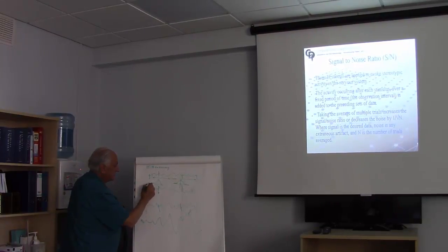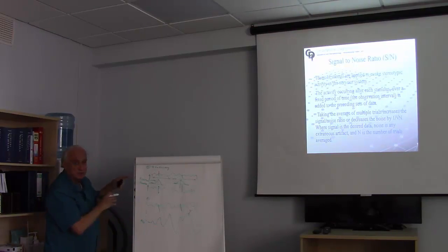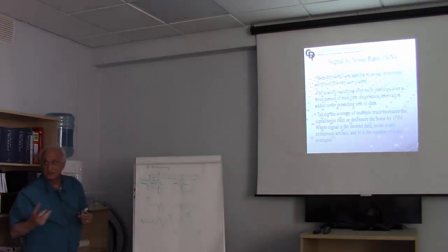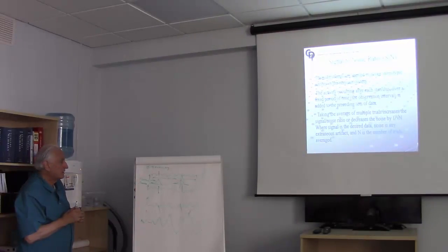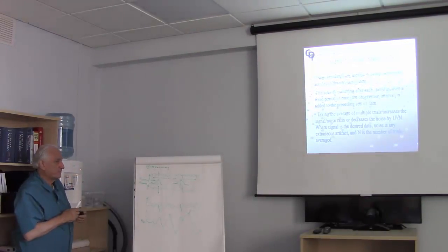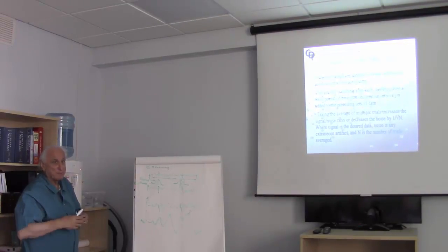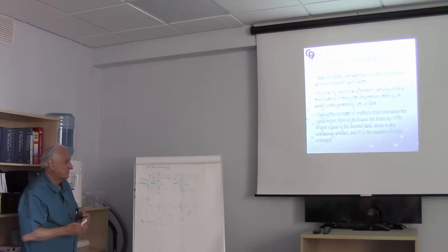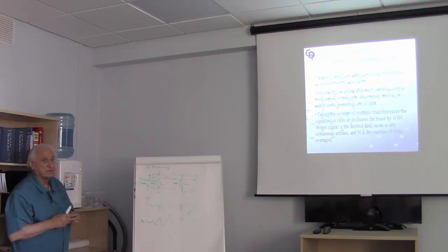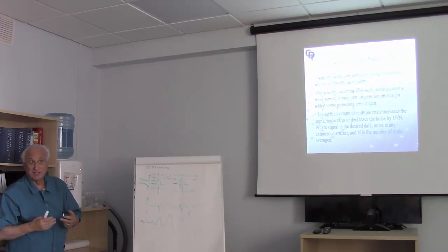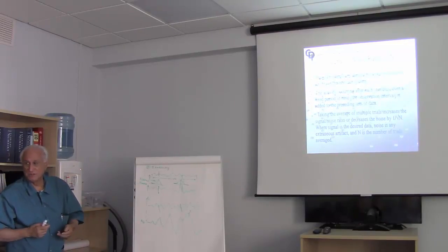The other thing that's fundamental is that the distribution of the data is normal or Gaussian. So those two assumptions are what underlie all this extraction of signals. It's important to have that model in your mind, because if for some reason the fundamental properties of the data are changing rapidly, it can change the value of the average. If the distribution is skewed for some reason, it can change the value. You may not be able to determine it, except that you're getting a result that doesn't make sense. That's maybe the only way you can determine it.